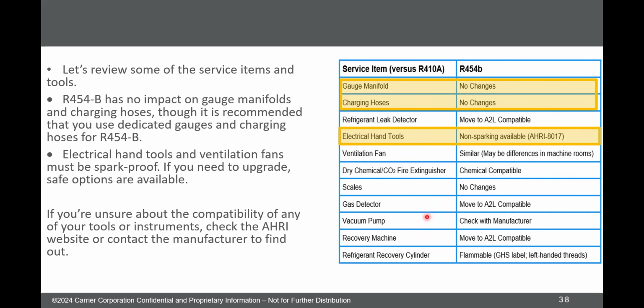Anything with a motor in it has to be A2L compatible listed. So recovery machine, vacuum pump, anything with a motor has to be basically a non-sparking motor. It has to be listed as A2L by that manufacturer. So some of the stuff guys own is totally fine. In fact, a lot of what they own is already fine.